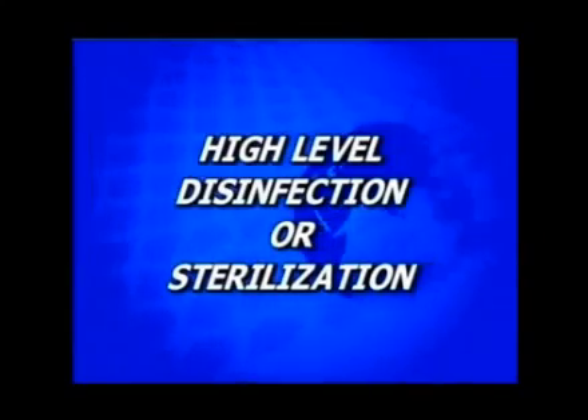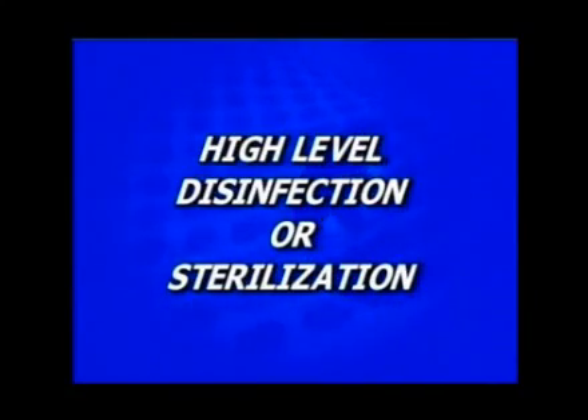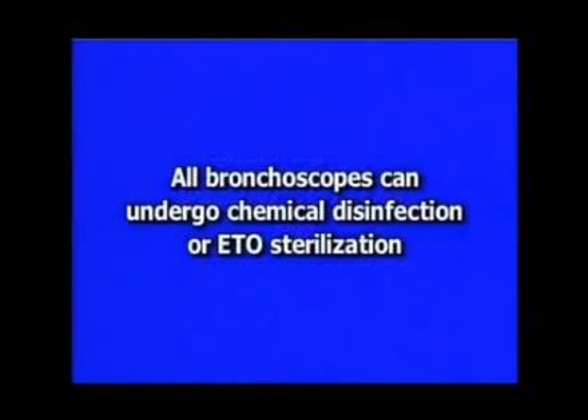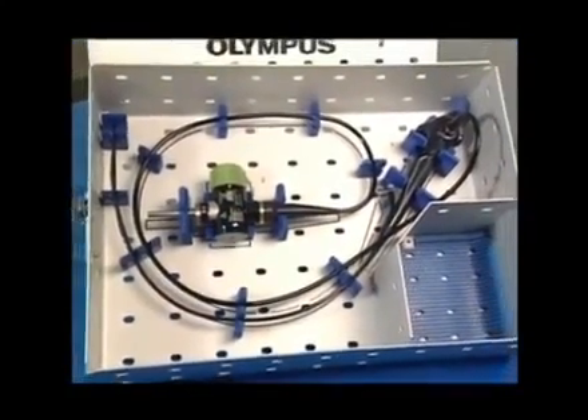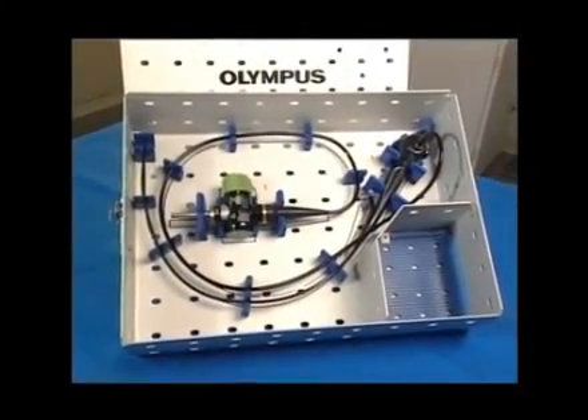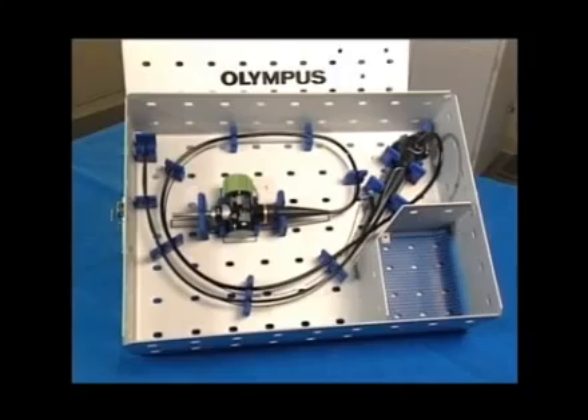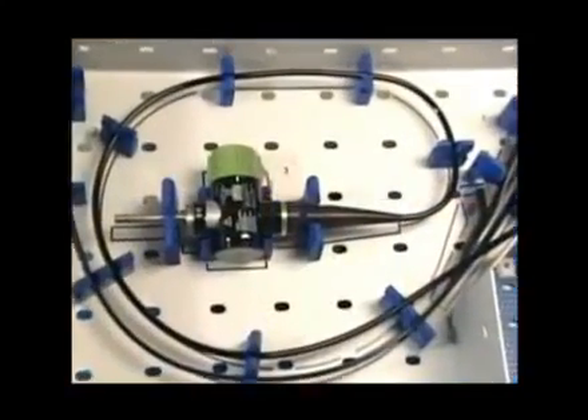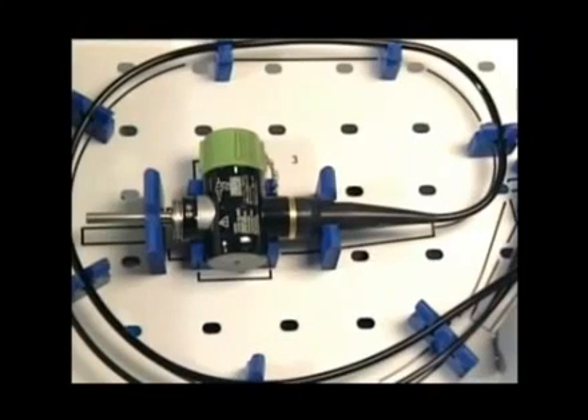The next step in reprocessing the bronchoscope is either high-level disinfection or sterilization. All Olympus bronchoscopes can undergo chemical disinfection or ETO sterilization. In addition, certain EVIS Exera II bronchoscopes may be steam sterilized after placing them in an appropriate protective tray. Note that autoclavable bronchoscopes have a green water-resistant cap and a gold band.